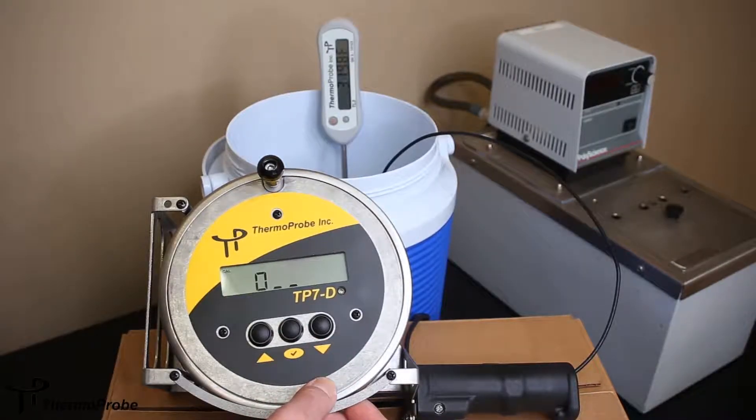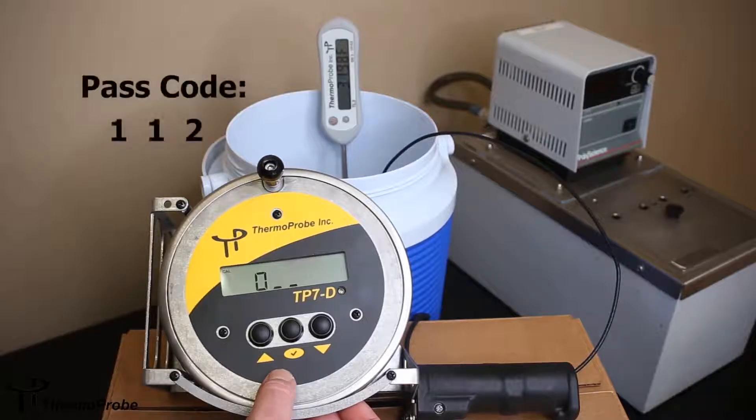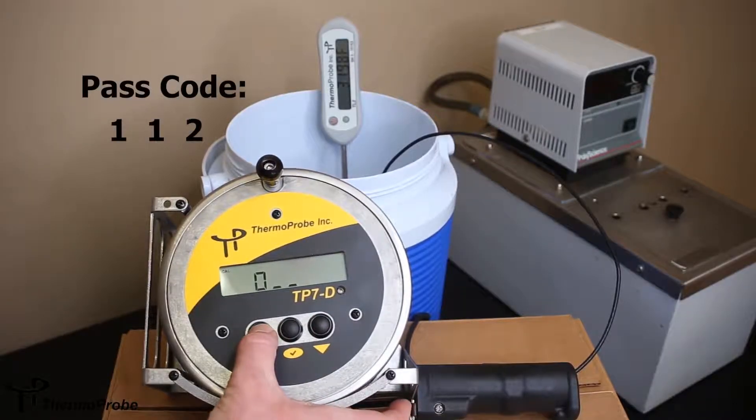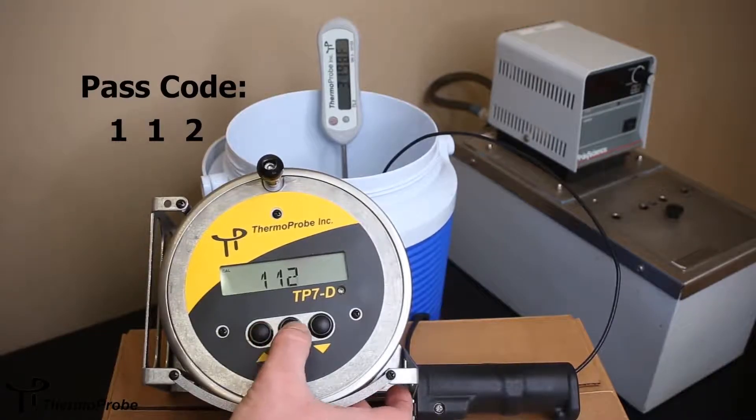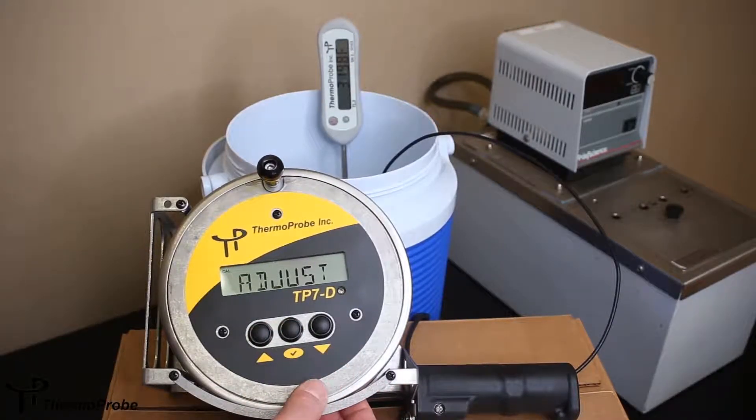To get into calibration, it requires a three-digit password to ensure it's not changed by accident. The password is 112. You use your up and down arrows to increment: one, one, two. That gets me into calibration mode.